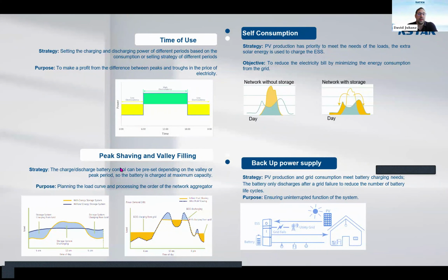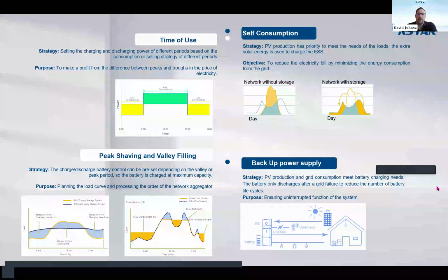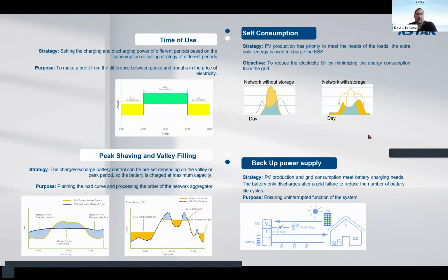We also have the peak shaving and valley filling solution as an operating mode, which is a dynamic control according to the consumption and the demand. It has the purpose of planning the load curve and processing the orders of the network aggregator, so it needs to be cooperated. And we also have the backup power solution. It has the strategy that when the AC power is out, the battery can only discharge when there is no grid. For this solution, the static transfer switch, the STS device, is also needed.